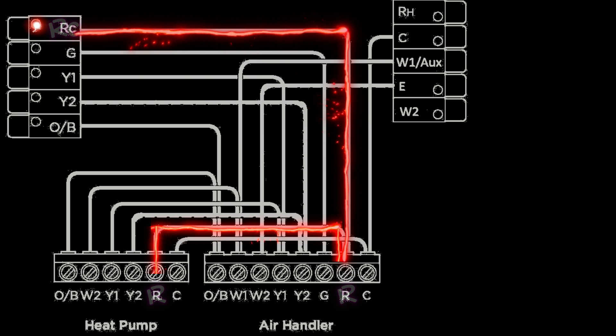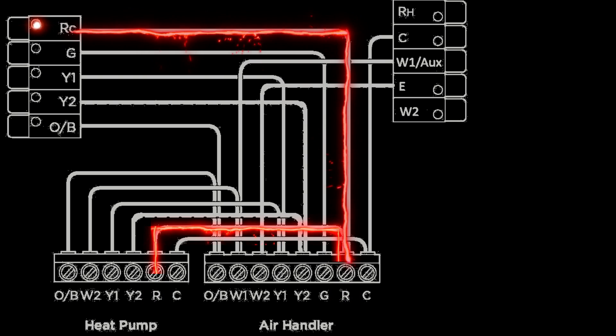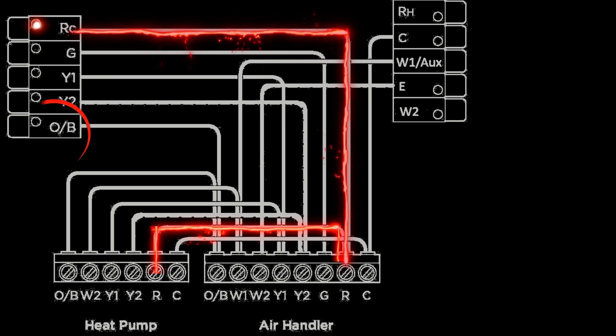So what I'm going to cover now are the terminals that a heat pump thermostat activates in both heating and cooling modes. These terminals get powered either way. What actually determines heating or cooling in a heat pump system is that O/B terminal there. But what I'm about to go through gets powered in either mode.